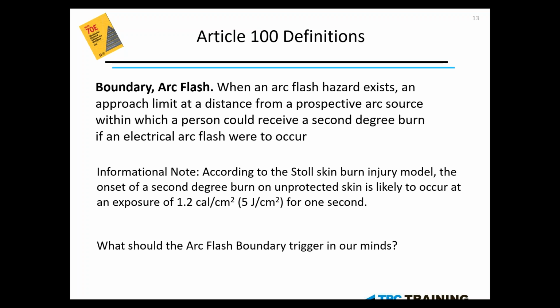Next, I'd like to talk on boundaries. Our arc flash boundary is our first one I'd like to identify. There are 3 boundaries in the code book that we must adhere to. The first one being the heat boundary, or typically the outermost boundary known as the arc flash boundary. This is a boundary that exists when an arc flash hazard exists. If something cannot be put into a de-energized state, we must protect against that hazard. So our outermost, typically our outermost one, I should say, is known as the arc flash boundary. It is our heat boundary.